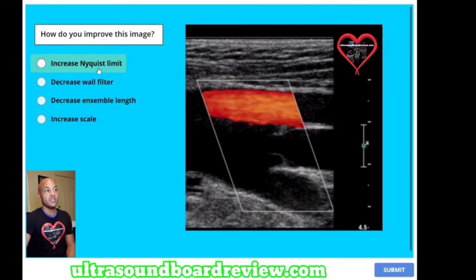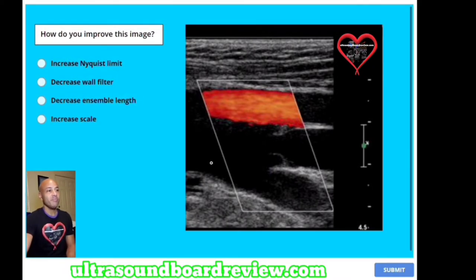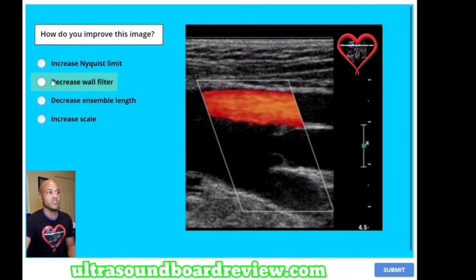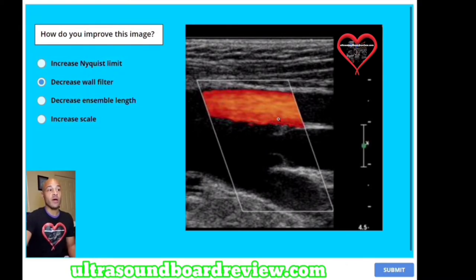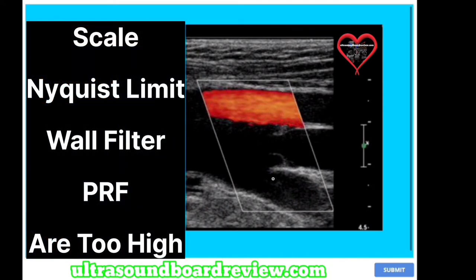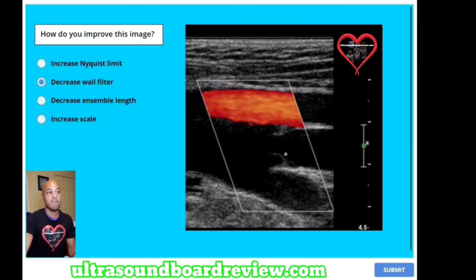How do you improve this image? A) increase Nyquist limit, B) decrease wall filter, C) decrease ensemble length, or D) increase scale? Based on the choices, we're going to decrease something because something is turned up too high. Decrease wall filter is the best choice. You're not going to decrease ensemble length, you're not going to increase scale because it's already increased, and you're not going to increase Nyquist limit because that's already increased. Your scale, Nyquist limit, wall filter, and PRF are all turned up too high, eliminating color Doppler in this area while preserving it elsewhere. Once we decrease those settings — because when you change one, they all change together — this will fill in. Always choose the best option.